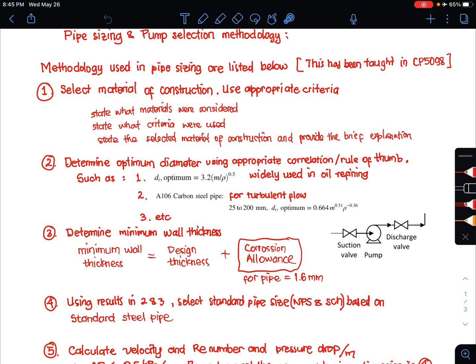There are many other correlations available. One important thing to note is the difference between line types. Because you will be designing both the suction line and the discharge line, you need to apply a rule of thumb on the diameter ratio. The suction line will typically use a larger diameter than the discharge line, so that the discharge line has a higher velocity.